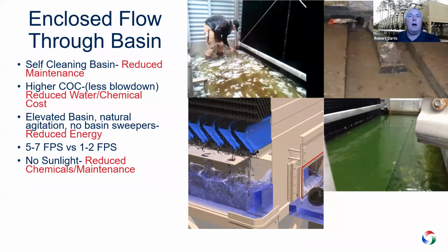Now we keep the solids suspended so that they can go out to the cleanup system and be cleaned up, filtered out, or go out the blowdown as opposed to settling in the tower. That has allowed you to reduce your maintenance on cleaning basins out, because it's a self-cleaning basin. In addition, because of us keeping those solids suspended, we're able to have less water being discharged to the drain, which means that you reduce your water cost and you reduce your chemical treatment cost.